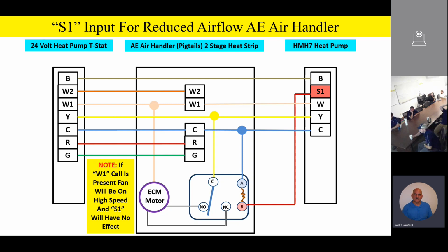Now, it should be noted that if I get a W1 call, either from the thermostat for auxiliary heat or when the unit goes into defrost, we're going to command a higher speed tap, because remember, on the ECM motor, we selected high speed tap for auxiliary heat. So anytime I have an auxiliary heat call from the thermostat, or I get a defrost command from the outdoor unit, we get a W signal during defrost from the outdoor unit, we're going to switch and put a higher speed command on that ECM motor, and it's going to drive that up to our high speed tap.